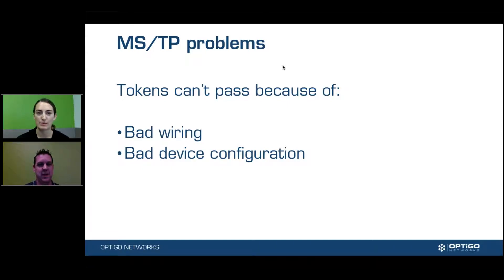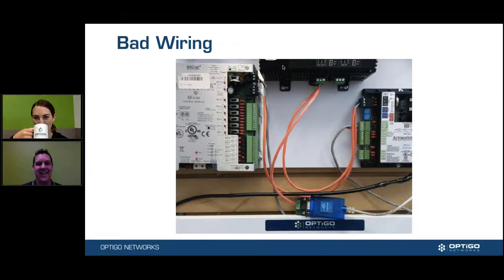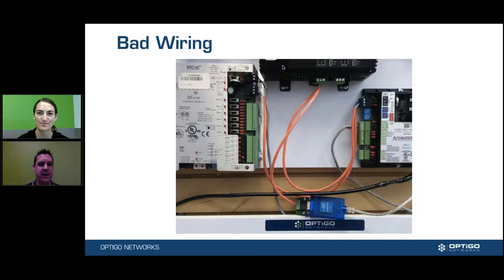So how do we end up in that situation? Well there's a lot of ways. Because we're only doing a short webinar here, we're only going to go through some of the top issues — this could be an hour or a full day training. One of the worst ways this happens is simply bad wiring. The electrician just threw the network in, wasn't paying attention, and then the tech is responsible for coming along and bringing the network up. Usually they don't always understand the network or the criticalities of it, and as a result some small problems happen and you have to go in and fix it.